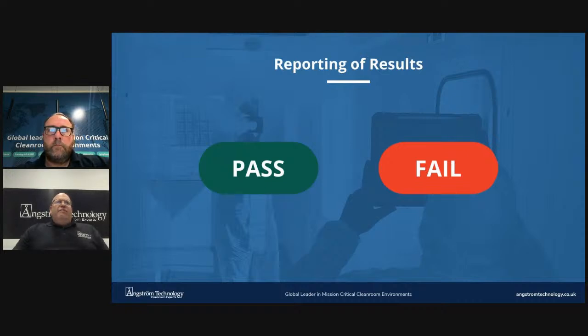Occasionally, requalification failure can be down to operational malpractice, such as incorrect gowning, contaminants being brought into the clean room by the users, and not following standard operating procedures defined by the client. Upon rectifying these issues by retraining or re-educating users, this may considerably reduce the contaminants, and the clean room may then pass the testing.